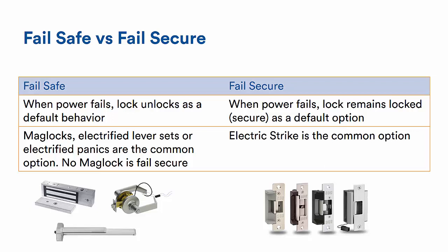Be aware that when a fail-safe product is used, the door will be unlocked whenever there is a fire alarm or power failure, which is an obvious security risk.